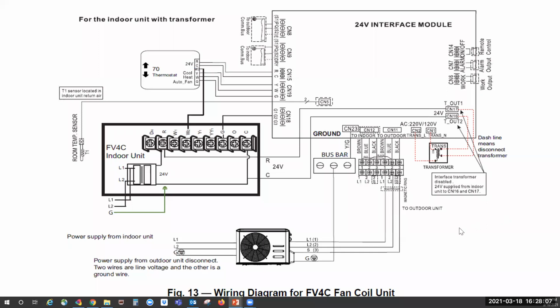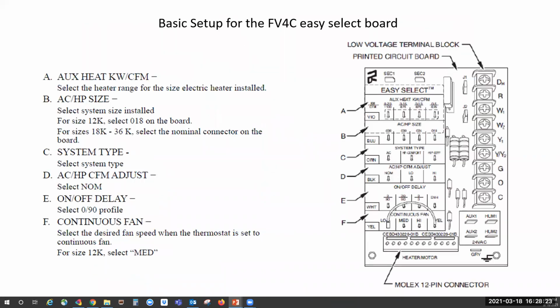And don't forget, you need to use a single stage heat/cool thermostat only, unless you're going to have your auxiliary heat come on separately from the heat pump, and then you'll need to use a 2-heat single cool thermostat. Something to remember: the G setting on these will be your continuous fan. So on the hybrid system, the blower will run continuously, while the outdoor unit will ramp up and down as needed, as the sensors tell it. So you will have to set the continuous fan per your installation manual for your 24-volt interface.